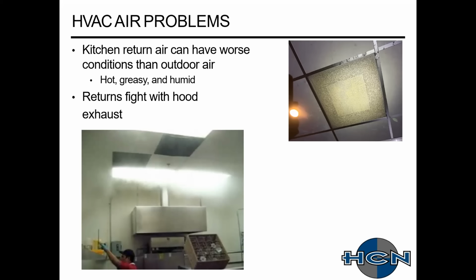A lot of times you'll see the dishwashers will have little, we'll say, eyebrow hoods, kind of based on the manufacturer. A lot of those conveyor type things really need to have that expansive hood that covers. With dishwashers, it's not a big thing because typically for the type 2 hoods, it's about 100 CFM per foot. Just having a little bit extra coverage, it's the same concept as the ovens. Getting that larger side coverage is going to help with that plume that you typically get off of those dishwashers. So it's captured appropriately and sucked right back out, versus trying to account for all this extra latent load that you can kind of see in this picture.